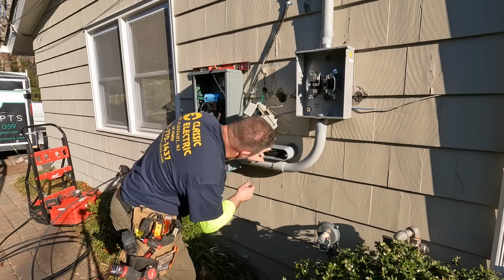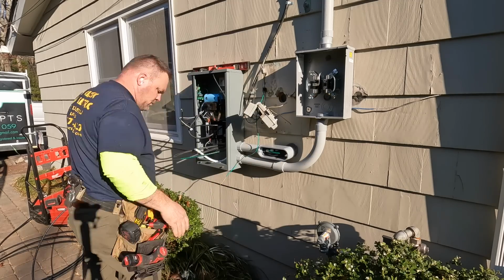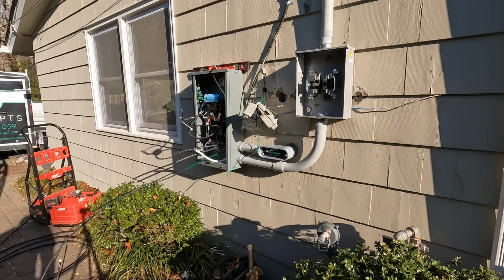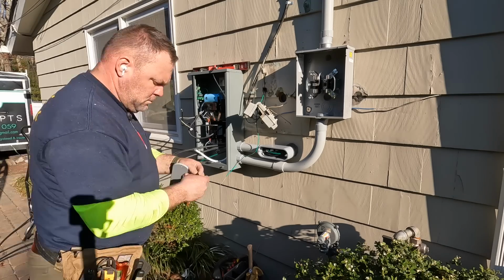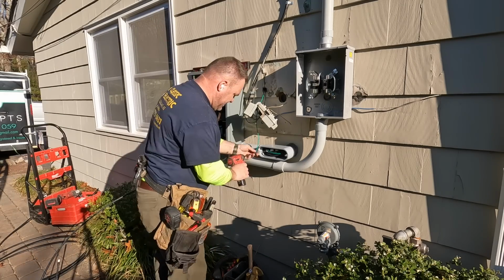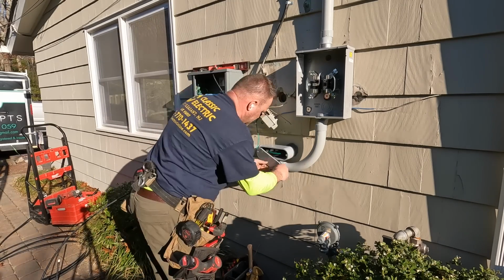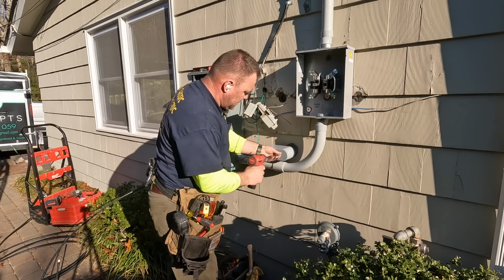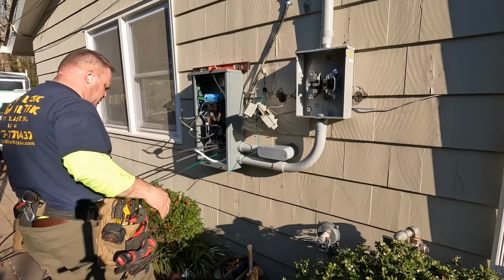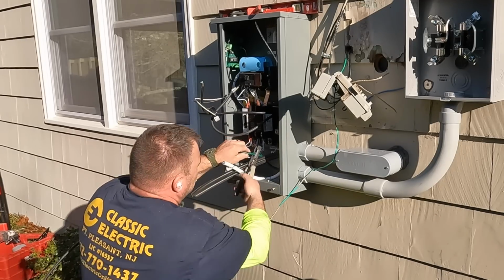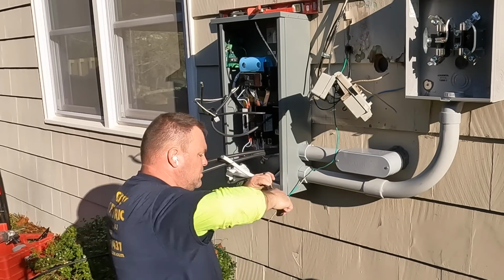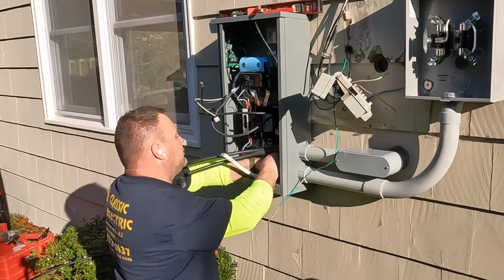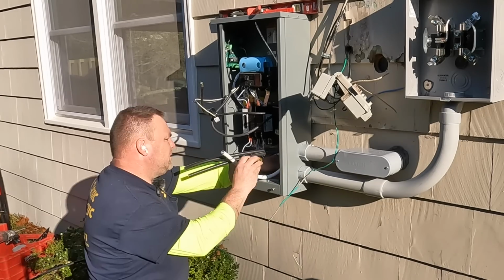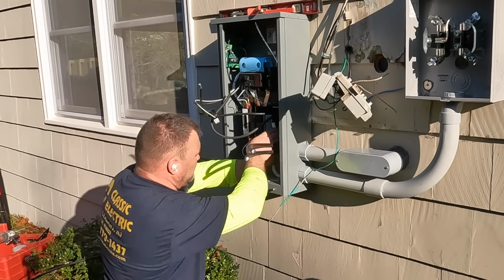We go over that at the IEC school in Somerset. And box fill, that's another big chapter that we cover. Obviously, your first year as an apprentice. So as far as the size of those conductors, they break them down into decimal points in the back of the NEC in Chapter 9. So you know exactly what type of conductor can fit in what size conduit, so that things are sized appropriately.